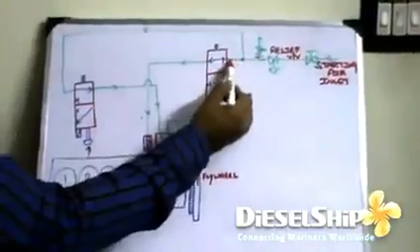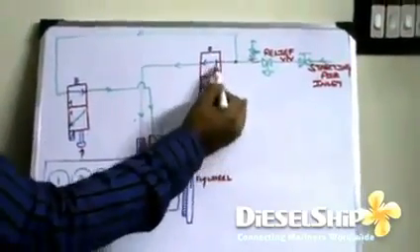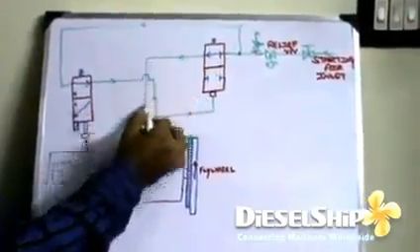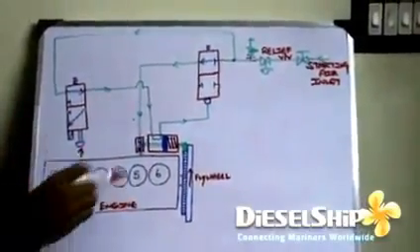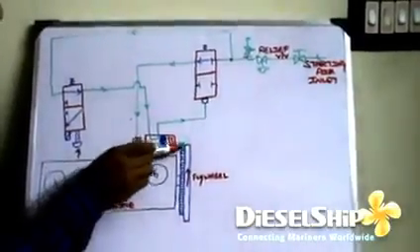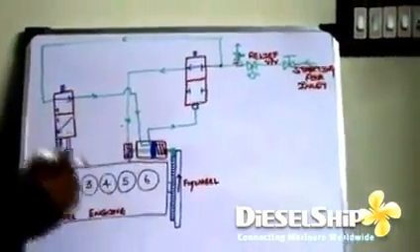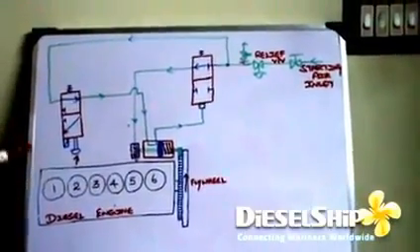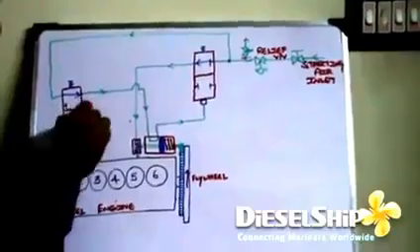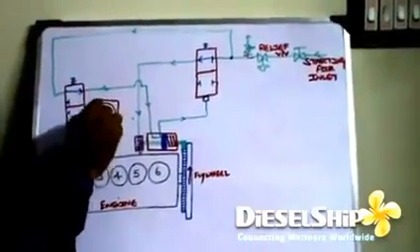Thus the main air which is waiting here, the valve shifts and then it passes through, rotates the vane and gets vented through a small hole. And as it rotates, the pinion rotates, thus the flywheel turns and then the engine picks up speed. And as the engine picks up the firing speed, I see the tachometer on the engine panel.